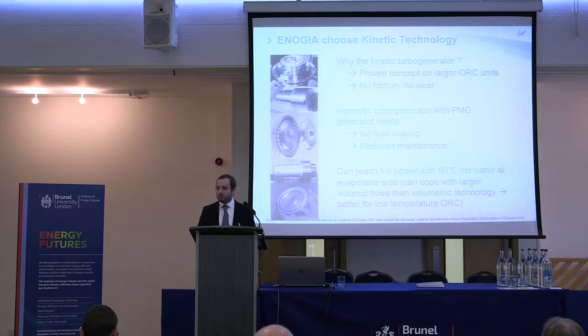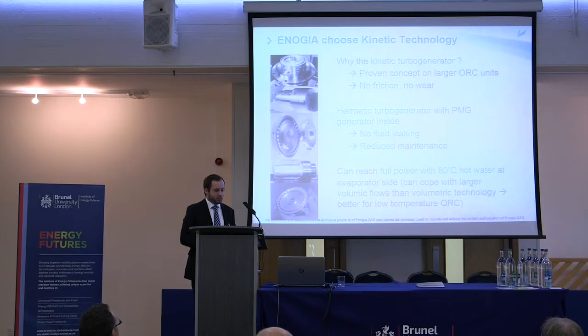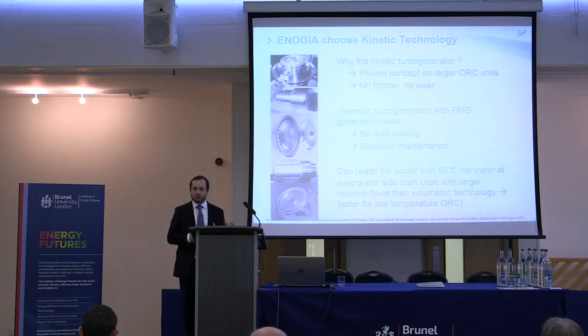Getting rid of the mechanical shaft seal was a key point we wanted to achieve, because a mechanical shaft seal causes fluid leaking, meaning you have to replace the working fluid, and it also requires maintenance since you have to replace the seal itself. So we succeeded in developing a small-scale ORC expander with no mechanical shaft seal, combining a kinetic turbine and a permanent magnet generator together in a single housing. Here you can see a picture of it.